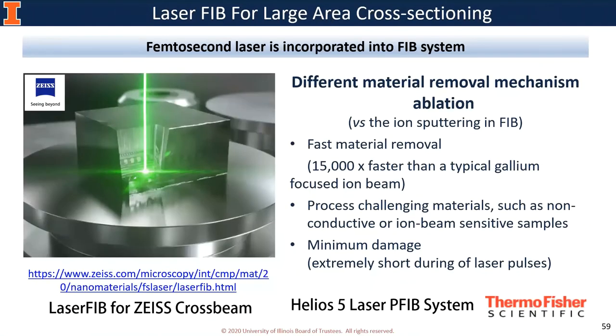Laser FIB is developed for extremely large area cross-sectioning. The material removal mechanism is laser ablation, enabling very fast material removal — 15,000 times faster than typical gallium ion beam. It can also process challenging materials such as non-conductive or ion-beam sensitive samples, and damage is minimized because of the extremely short duration of the laser pulse.